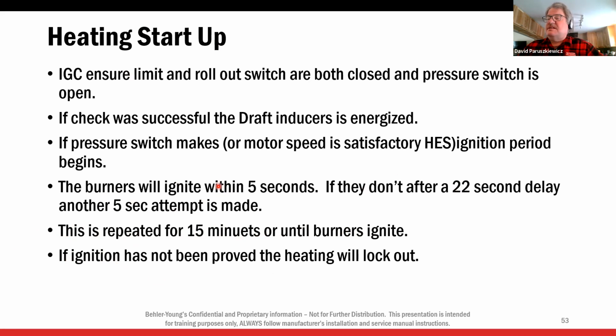All right. So the sequence of operation on heating especially, it really eases troubleshooting things. Call, inducer comes on, pressure switch sends a signal to the board, times out, opens the gas valve, starts the igniter. If the igniter lights, we send a signal, keep the valve open, and in a certain amount of time, the blower comes on. Igniter doesn't light after 5 seconds, we shut down the ignition attempt, wait 22 seconds, we try it again. After 15 minutes of failure to ignite, it locks out. All right, so if we understand that, it just makes it easier.